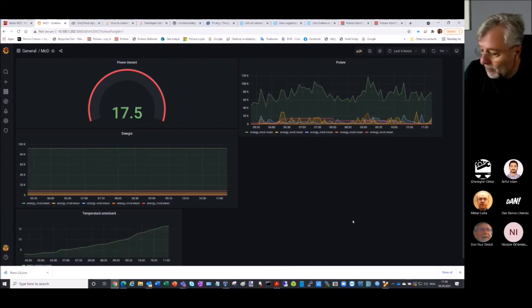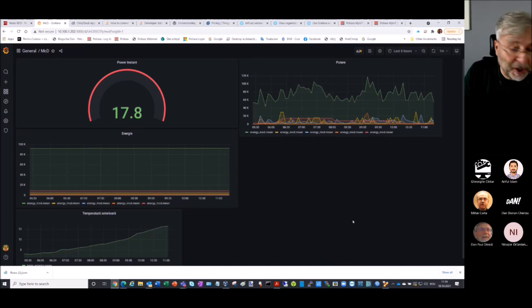So instead of keeping the data for 1 year every 5 minutes, you tell it to keep only every 30 minutes. That means that instead of 12 values per hour corresponding to a 5 minute update, you keep only 2, every 30 minutes. Sometimes for the client this is okay, because nobody will be interested to know how much power was consumed in 5 minutes in November last year. Probably he will be interested to know how much energy I used in 1 day, to give you an example. Of course, if the customer wants to keep all information, he can save it.